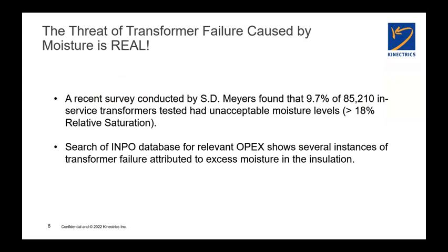Continuing with the theme of the reality of the threat of moisture, SD Myers, which is an oil testing organization, a laboratory, and a service company in the US, they have a very extensive internal database from all the oil testing that they've done over the years. And they conducted a survey of that data and found that almost 1 in 10 transformers in that database of 85,000 records had unacceptable moisture levels inside the transformer. Unacceptable being greater than 18% relative saturation. And because Kinectrics is in the nuclear space, we have access to the INPO database, and we searched the OPEX, and there's several instances where nuclear facilities have experienced transformer failures that can be directly attributed to excess moisture in the paper insulation inside the unit.